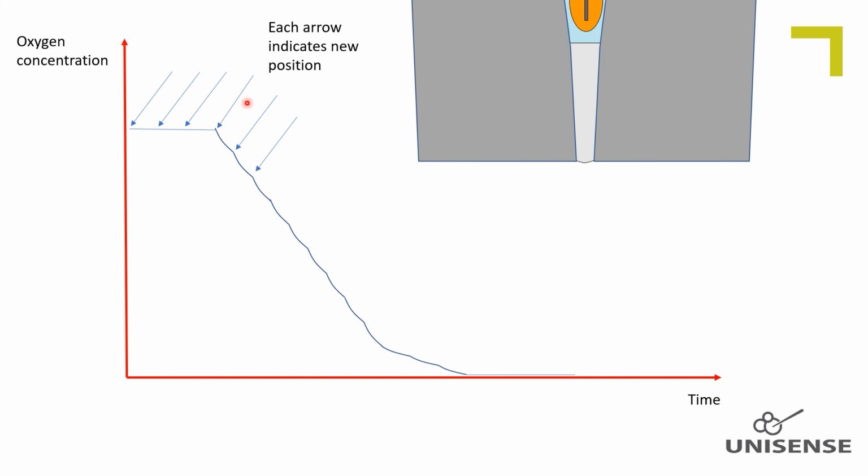The time between the increments are again chosen to be a few seconds longer than the response time of the sensor. What we see is that the signal does not reach a plateau within the chosen time between the increments. Looking closer into the signal change after an increment, we see that the signal still drops way longer than the response time of the sensor.